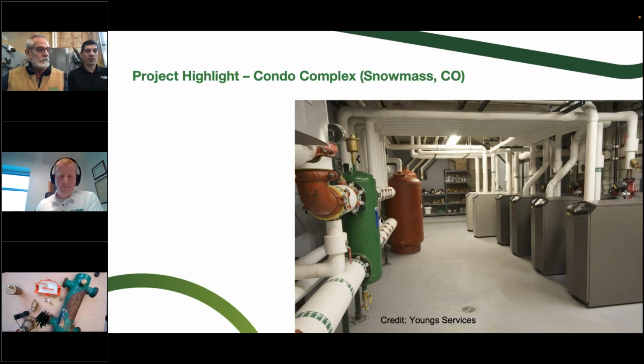In this case, before they did this big renovation, the property manager had to go to every piece of fin tube baseboard with a little cup when they changed tenants, which may have been once a week because it's a big ski condo complex, and bleed out airlocks in all the fin tube baseboards. Then there's rusty water on the carpet, and it was this big mess. They were able to prevent that from being an ongoing thing by separating the air well before it left the mechanical room, catching the bulk, the entrained, and the air dissolved within the fluid right there. That's the best way to prevent an issue before you even have to deal with it at the different terminal units.